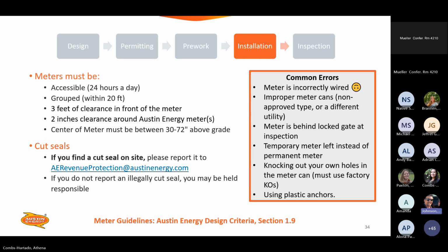A temporary meter left instead of a permanent meter. We have to have the blank and seal when we complete and approve the inspection. At that point, the blank and seal should stay until the meter shop shows up to open it and put their meter in. If there is a meter already installed, they will go hands off of it and that's it. They will kick it back to us and we'll have to investigate and see what's going on, which will delay the process of getting the customer their meter and their PTO to use their solar system. Knocking out your own holes in a meter can.